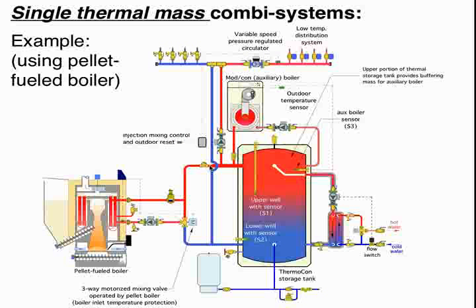Most of the pellet-fired boilers do that. The pellet-fired boilers, from a control standpoint, most of them do not look at what's happening with the zones. They only see 2 temperature sensors in the tank, an upper temperature sensor and a lower temperature sensor, and their sole control task is to basically, when that upper sensor drops to a certain value, they turn on, and they remain on until the lower sensor gets up to some higher value. They have no idea what's going on with the load.